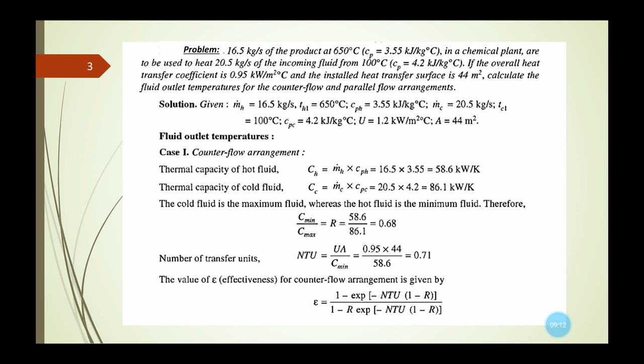Now the value of the effectiveness for this counter flow arrangement is mathematically represented as epsilon equals 1 minus e to the power minus NTU into 1 minus R, divided by 1 minus R times e to the power minus NTU into 1 minus R. If we put all the values of NTU and R, which are known to us, we can calculate the effectiveness, we are getting 0.443.